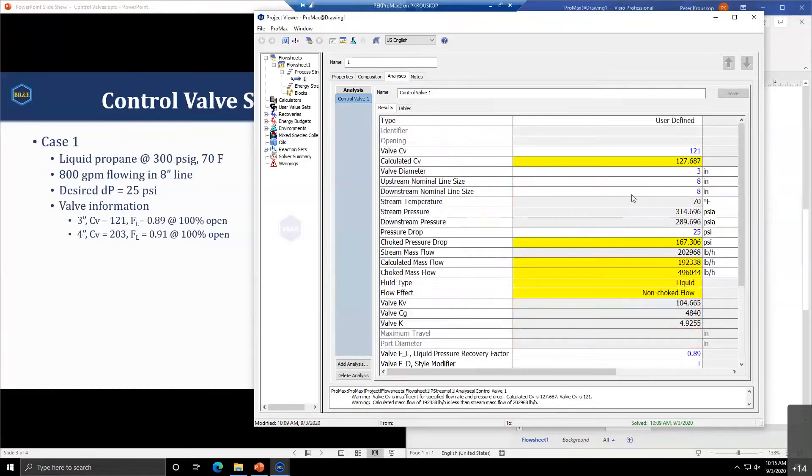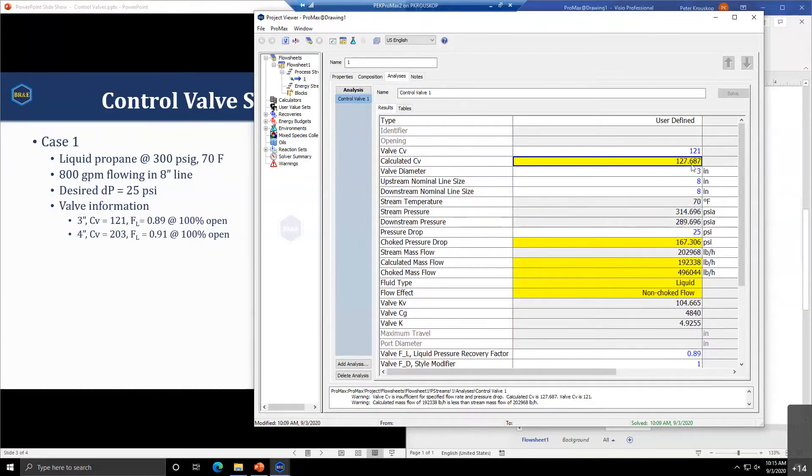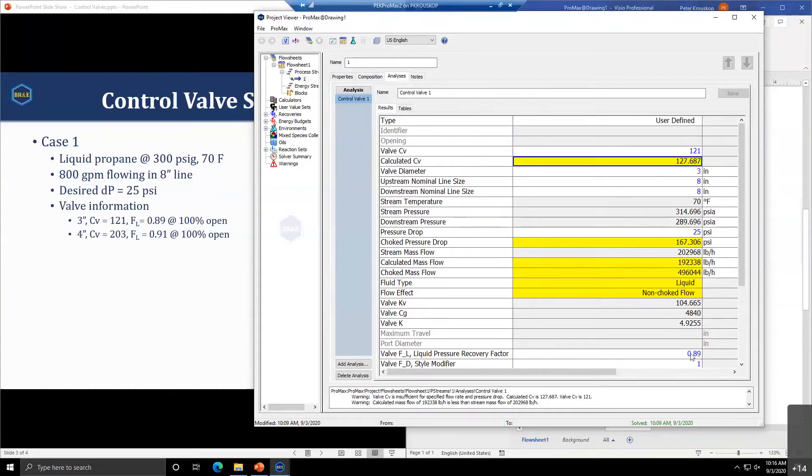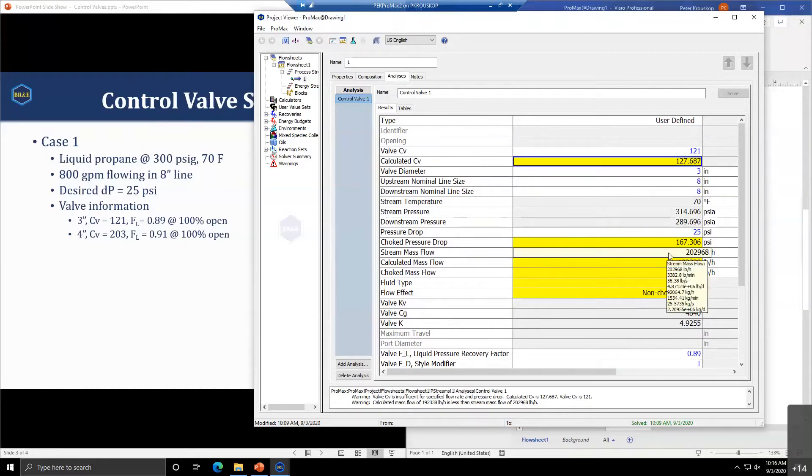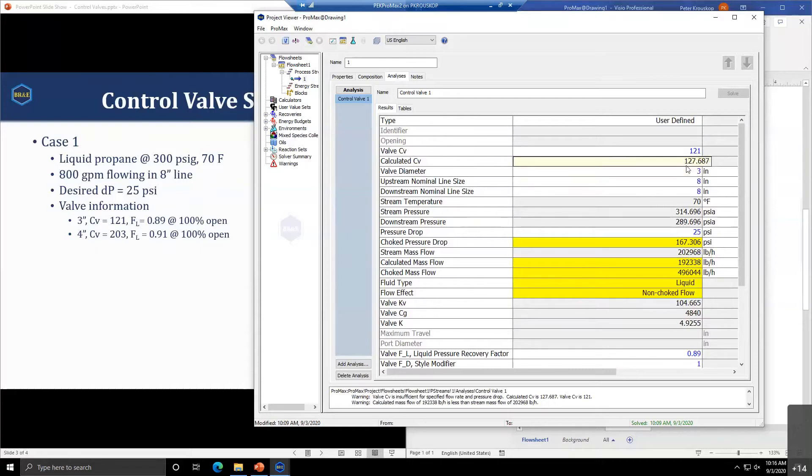The big reason that all of these are yellow right now is that this calculated CV is larger than the valve CV. The calculated CV is obtained by taking this pressure drop and stream flow rate with this FL to determine what CV would be required to allow this flow rate through a 25 pound pressure drop.